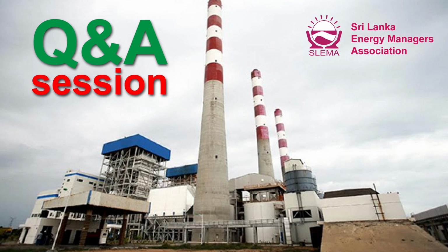Can't we use frequency control from the plant? Frequency control from the plant is not that readily available, because the chemical energy of the coal is being provided to the boiler, and from the boiler it takes a considerable amount of time, about 8 to 10 minutes, for that energy to reach the generator. You have to heat up the flue gas, get the steam out, water needs to be boiled, and then that steam has to reach the superheaters and go through all the heating. So when you introduce coal, the pressure won't change. The fuel change will only be visible after 8 minutes.